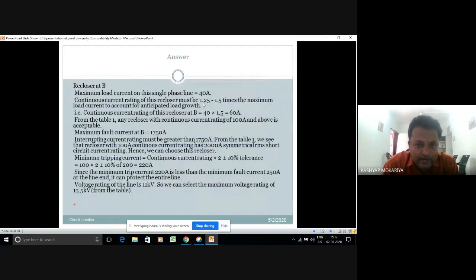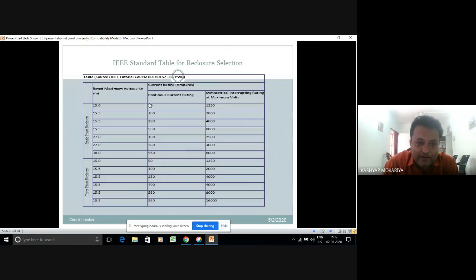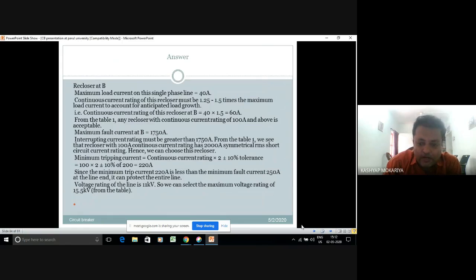Continuous current rating of the recloser must be 1.25 times to 1.5 times the maximum load current to account for the anticipated load growth. So multiply it by 1.5, you will get 60 ampere. Now you have to go to table 1 and fetch the suitable next available rating. It is 100 ampere. It is acceptable. So you can see after 50 ampere the next rating is 100 ampere here. It is mentioned.